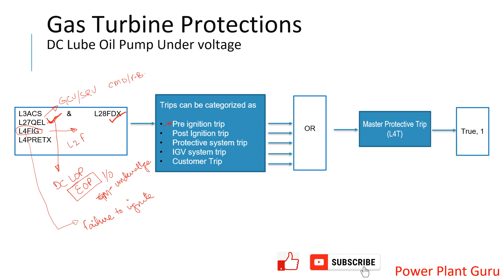When a command is given for ignition and the spark plug produces a spark, but that spark is not converted into a flame strong enough to be scanned by the flame scanner, a timer — the startup timer — begins. If the flame scanners do not detect any flame before this timer lapses, then L4FIG is activated. Combined with L28FDX already being active, these two signals together form the pre-ignition trip signal which goes to L4T.